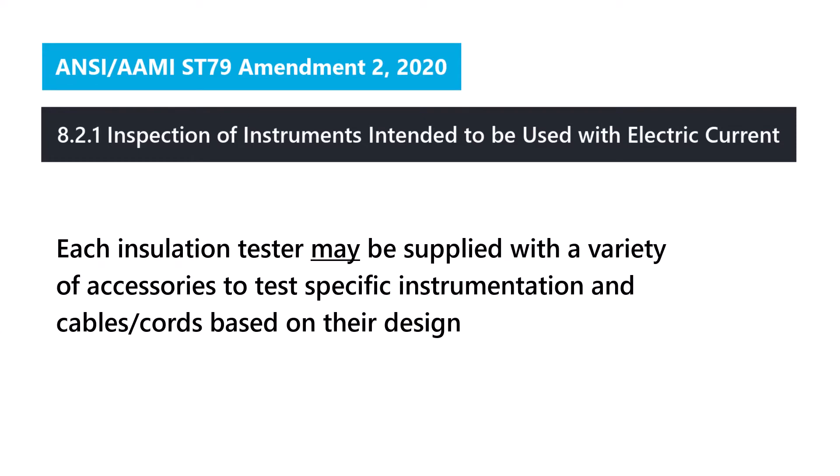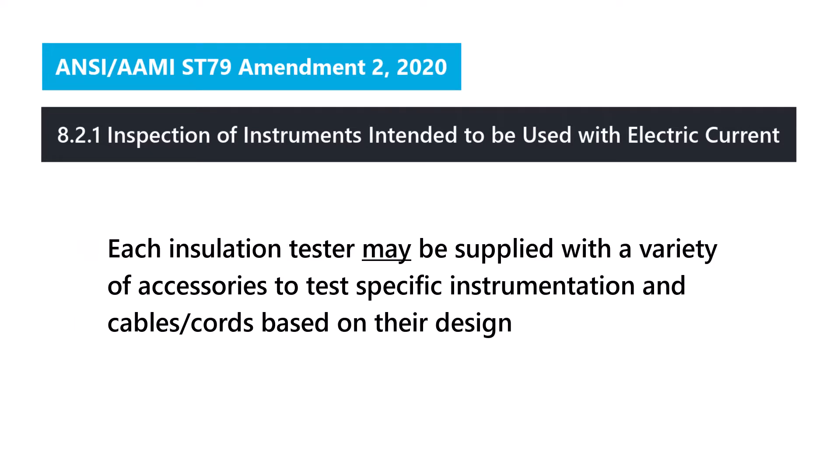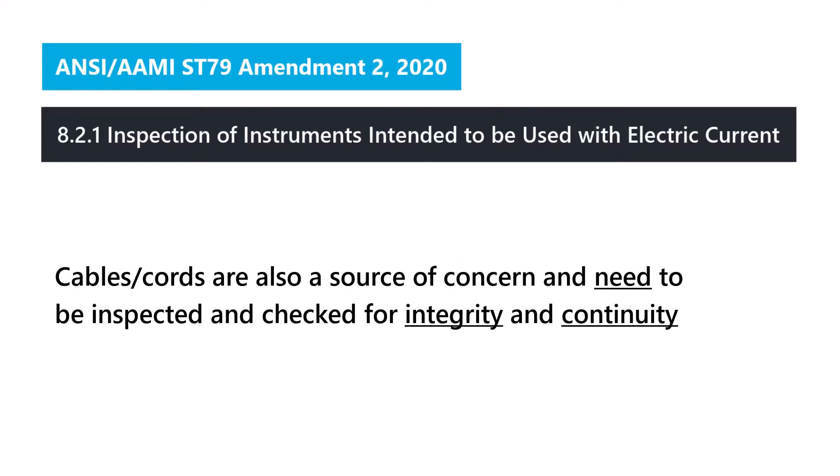AAMI states that each insulation tester may be supplied with a variety of accessories to test specific instrumentation and cables and cords based on their design. Cables and cords are also a source of concern and need to be inspected and checked for integrity and continuity.